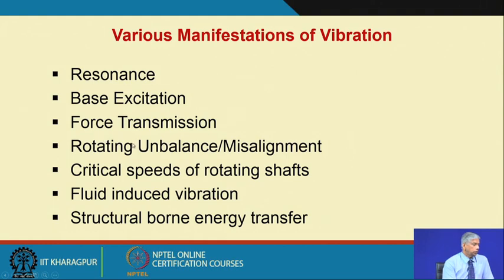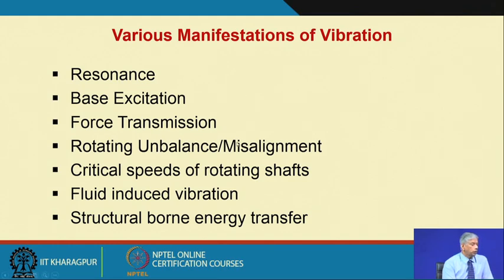Another source of vibration is rotating unbalance and misalignment — these are among the very common rotating machinery faults: unbalance in the rotating shaft or disc, and misalignment between two shafts connected by a coupling or supported on bearings. These give rise to vibrations. In rotor dynamics, critical speeds occur because shafts are flexible and have many natural frequencies; machines must avoid operating at critical speeds so resonance does not occur.